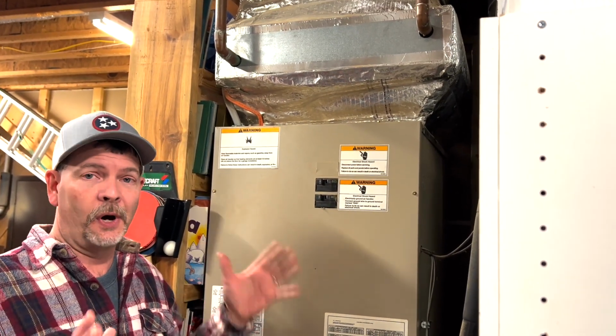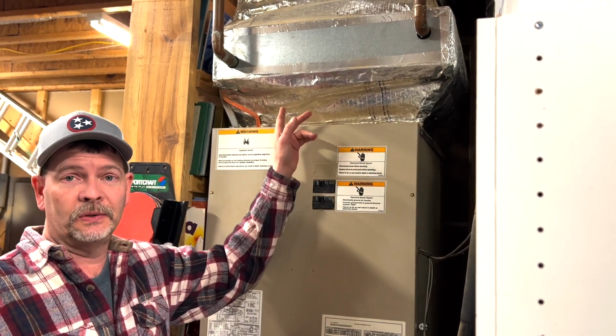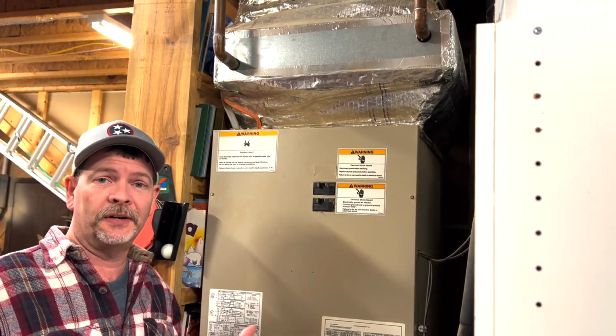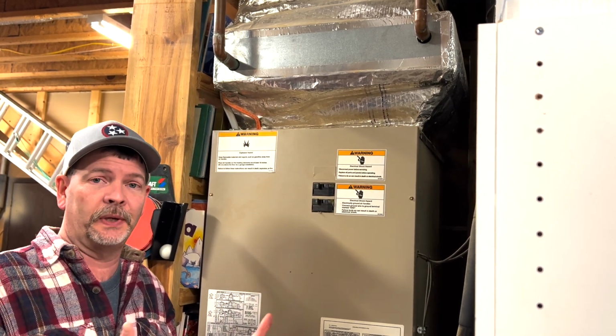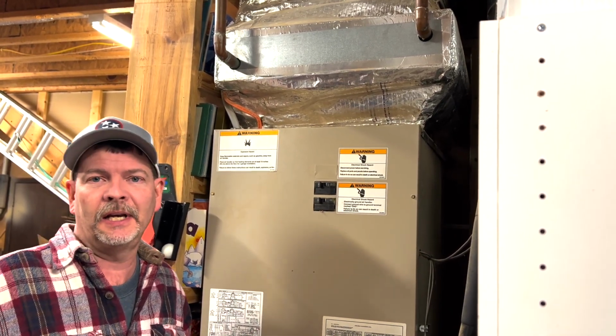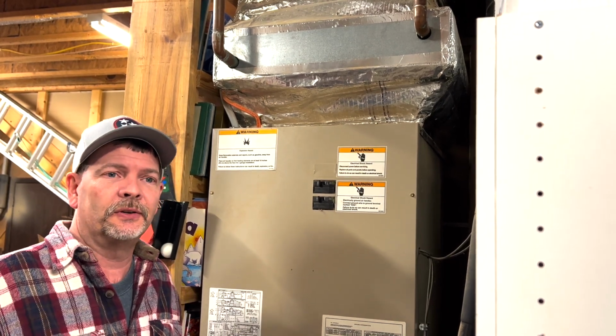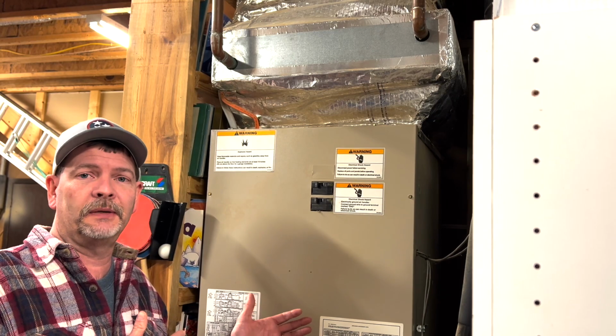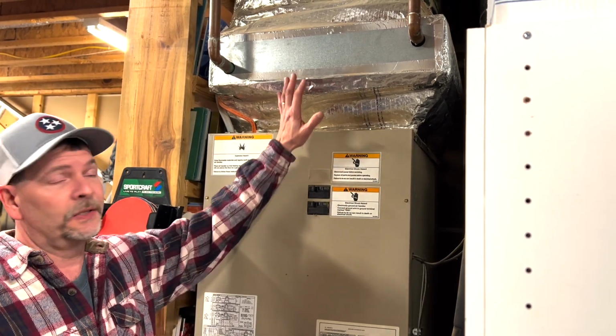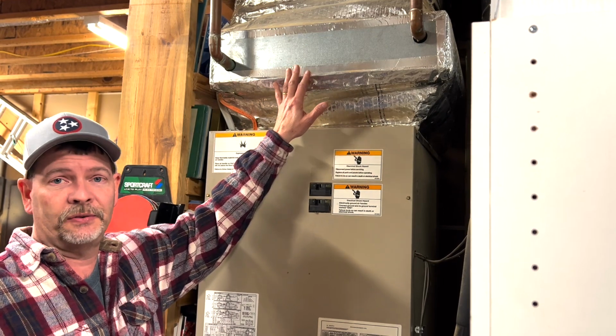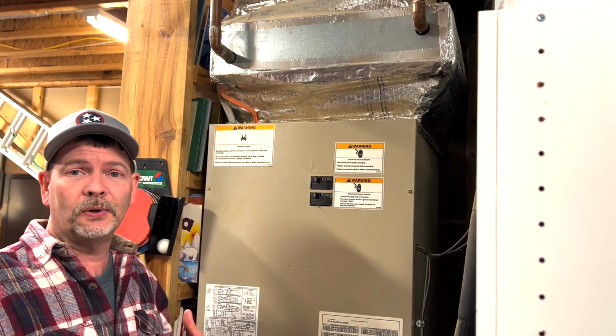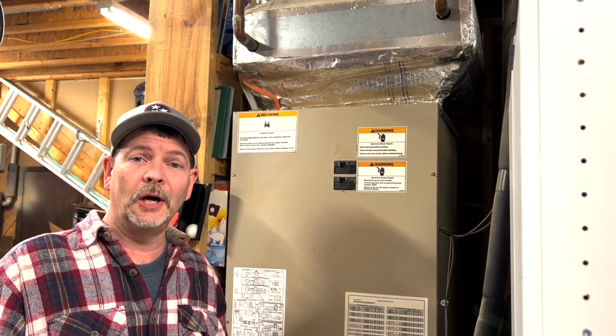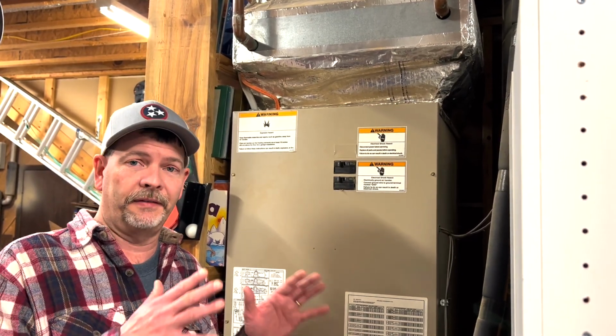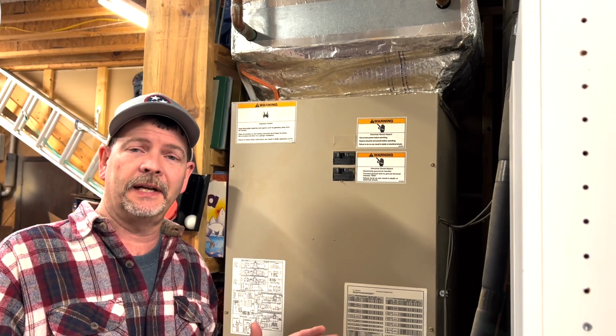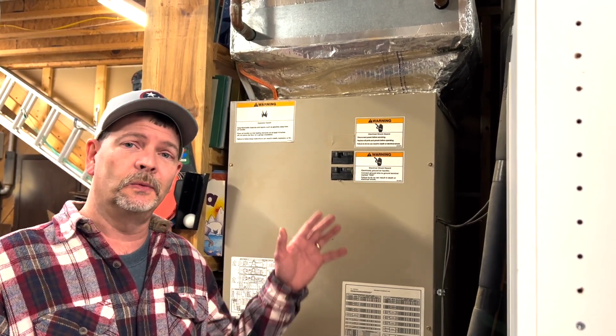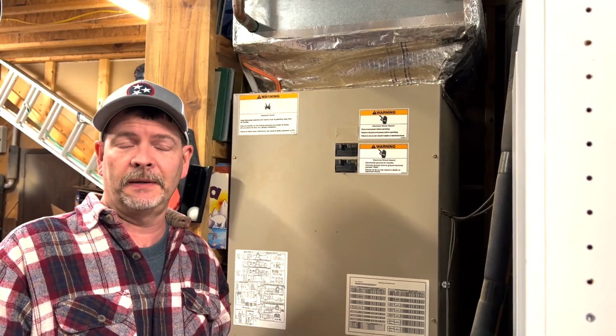The water coming from the stove is 185 degrees when it leaves the stove. There's probably some heat loss between here and the house, since the stove sits maybe 100 to 110 feet away, so there's some heat loss underground as it travels. Let's say it's around 170 degrees when it runs through the coils in the heat exchanger, so that's super hot air coming through the ductwork. There's a noticeable difference in the temperature of the air through the vents when it's fed through the heat exchanger and wood stove versus the heat pump running by itself.